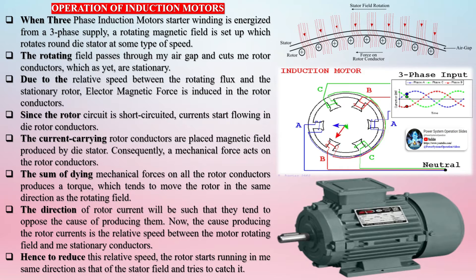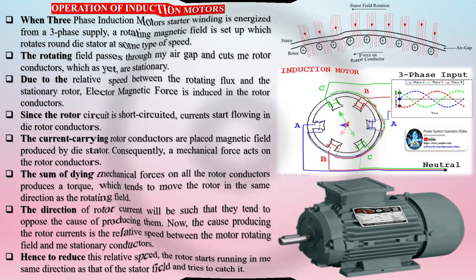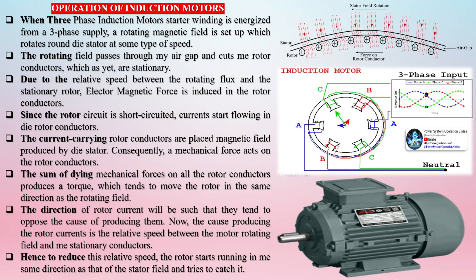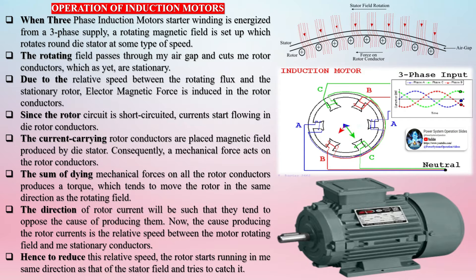The current-carrying rotor conductors are placed in the magnetic field produced by the stator. Consequently, a mechanical force acts on the rotor conductors. The sum of these mechanical forces on all the rotor conductors produces a torque which tends to move the rotor in the same direction as the rotating field. The rotor current direction is such that it tends to oppose the cause producing it — the relative speed between the rotating field and the stationary conductors — so the rotor starts running in the same direction as the stator field and tries to catch it.